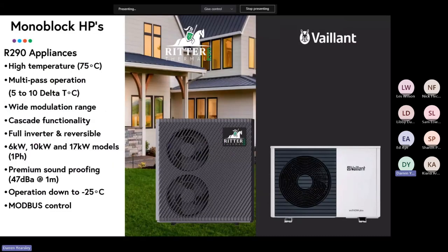Okay, so this is an example of what the units look like. They're monoblock, and what monoblock means is that refrigerant never leaves the appliance. We're only circulating water backwards and forwards, and they have basic system components built in. So primary circulation, safety valve, those components are actually inside the jacket. So hydraulically, when you come to connect to them, it's very simple. On the primary side, you don't need to do reverse return because each unit has its own pump and controls its own speed across the exchanger to optimize for that 5 degree difference. And again, it's comfortable, multi-pass, 5 or 10 degree difference across the appliances is perfect.